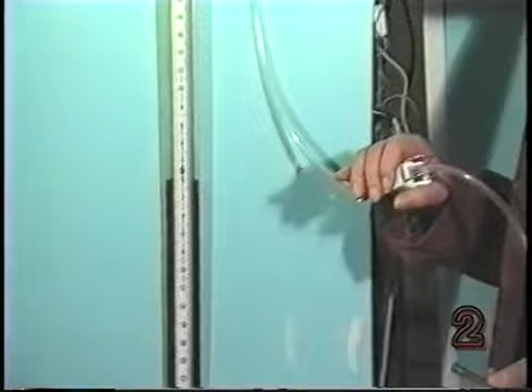When calibrating for intraoral air pressure, we use a device that's referred to as a U-tube water manometer. By displacing the water column and measuring the distance that the column moves on each side, we can express the subsequent pressure measurements in terms of centimeters of water. We record the calibration signal produced and use it for later measurement.